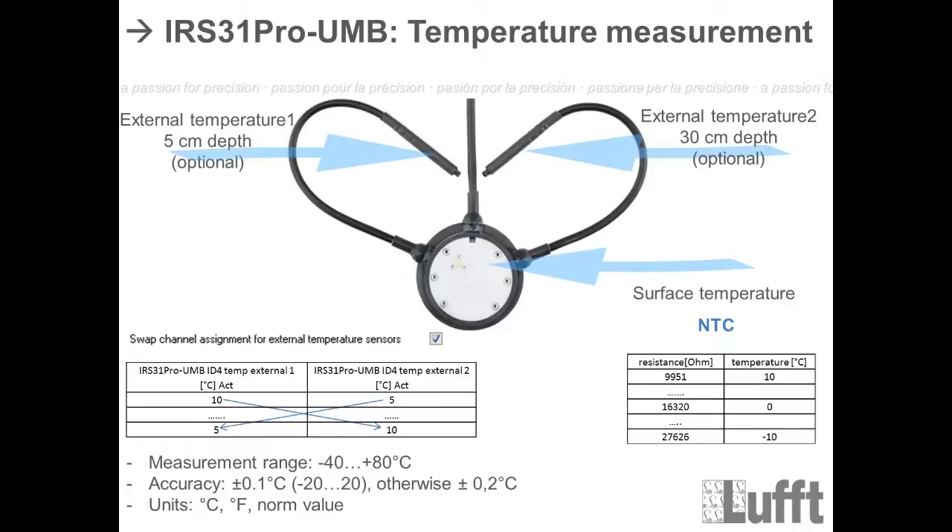The measurement range for temperature is between minus 40 degrees Celsius and 80 degrees Celsius. The accuracy is plus/minus 0.1 degrees Celsius between minus 20 and 20 degrees, otherwise plus/minus 0.2 degrees Celsius. The available units are degrees Celsius, Fahrenheit, and norm value.